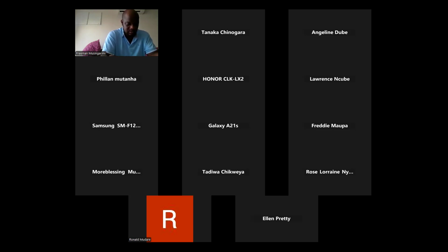We're going to talk about efficiency in UPSs, right? There's no 100% efficiency in a UPS, unfortunately. They start from around 97, those are the best ones. Some may tell you they're 98, but it's almost untrue. Why? Because you have a lot of losses. One is heat. All these components, the booster and the rectifier, it's not just one. There are components that are going through these heat losses. So if you're asked whether you can ever get 100% efficiency on a UPS, you must say, no, not possible, right?